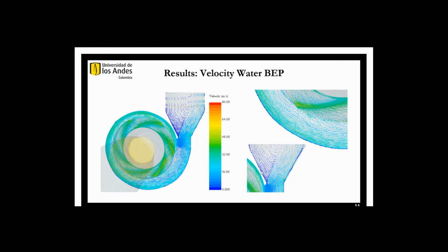This is because a higher flow will translate into a higher speed, given its definition, as long as a certain transversal zone is maintained. It should be noted that a high flow rate is not always good, as an inadequately high flow rate could cause cavitation. It's important to operate pumps at an optimal flow rate to avoid this phenomenon. In this case, the best efficiency point.